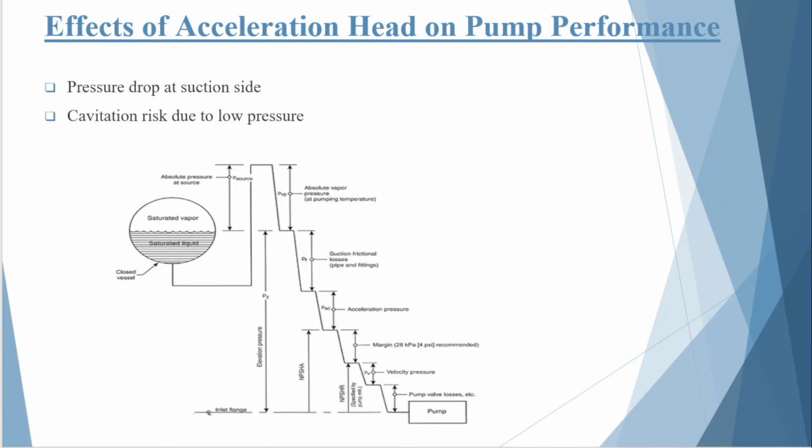so important from an operational perspective. One of the first consequences is a reduction in suction pressure. During the suction stroke, part of the available pressure is consumed in accelerating the liquid column. As a result, the actual pressure at the pump inlet decreases.